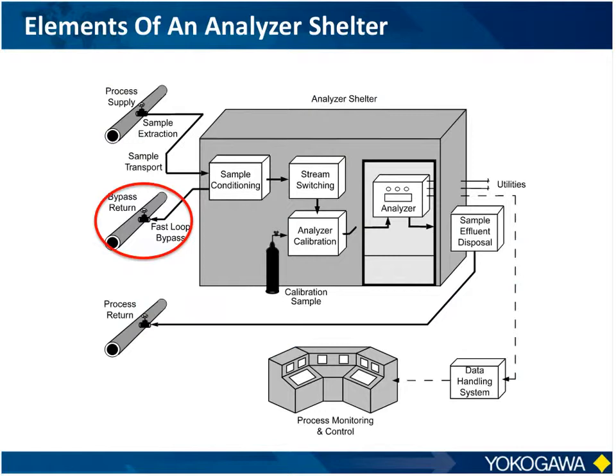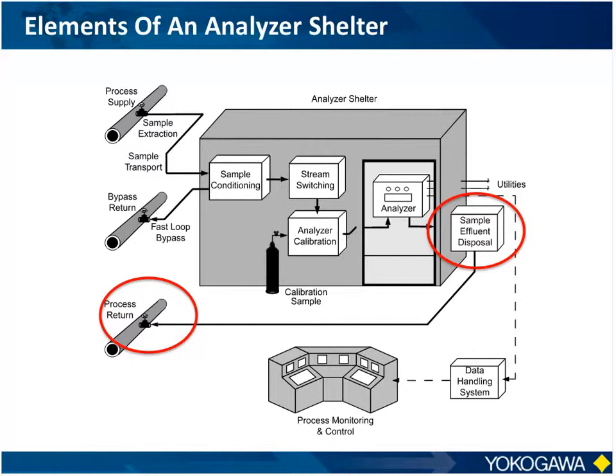The unused portion of the sample would be returned back to the process. You can't just vent it into the air, not like the good old days when air pollution laws weren't quite so strict. There might be some effluent, liquids or different gases that are left over from the slop during the measurement, and they also must be returned either to the process, a flare line, or some type of recovery system.